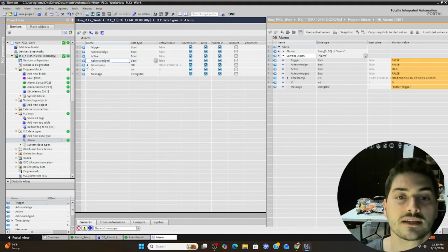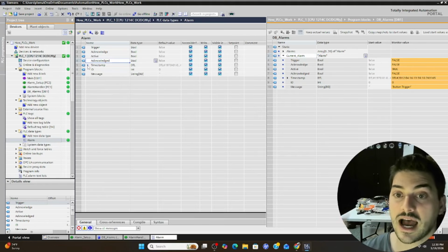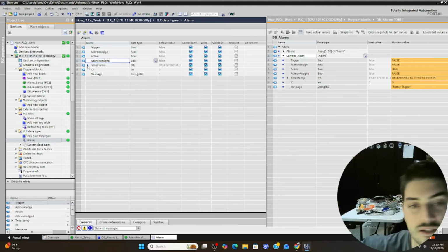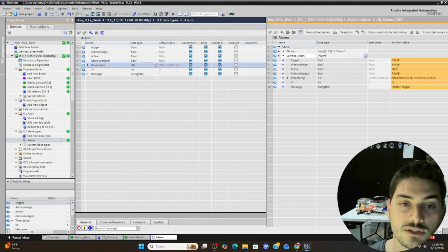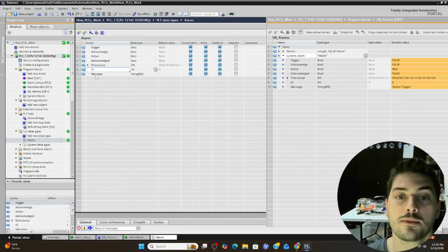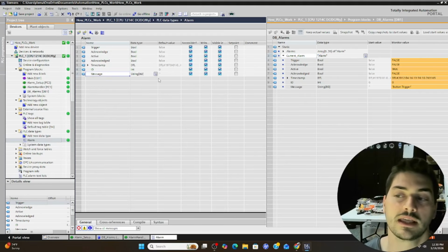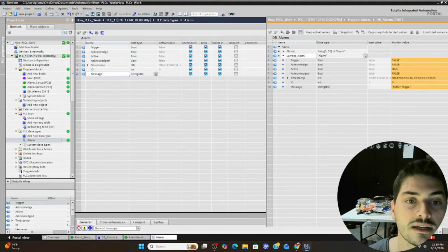And then just practically speaking, we'll want to keep track of the last time, the timestamp that the alarm triggered. This is really useful if you were to tie this to an HMI or some sort of SCADA software so you can track alarms over time. And then we'll just give a couple identifying things. So ID and message: ID could just be enumerated 1 through 20, and message could be like, here's the thing that just happened. So you put that information again on an HMI.